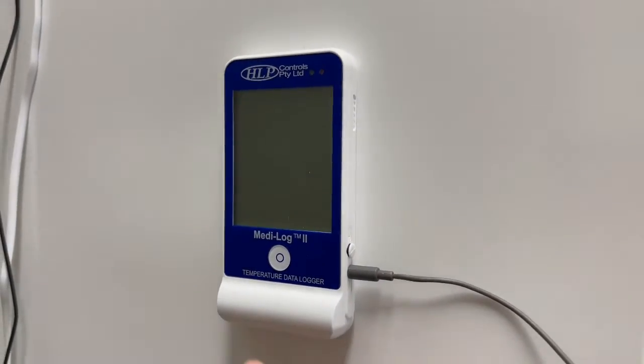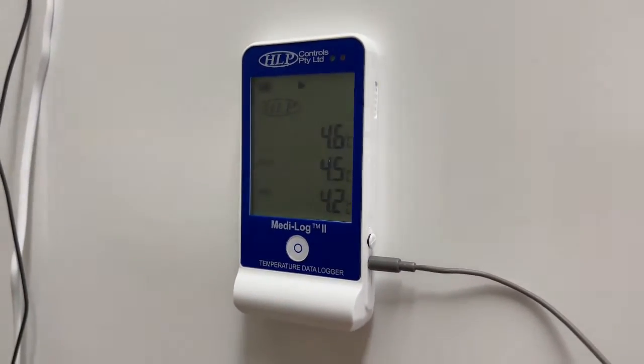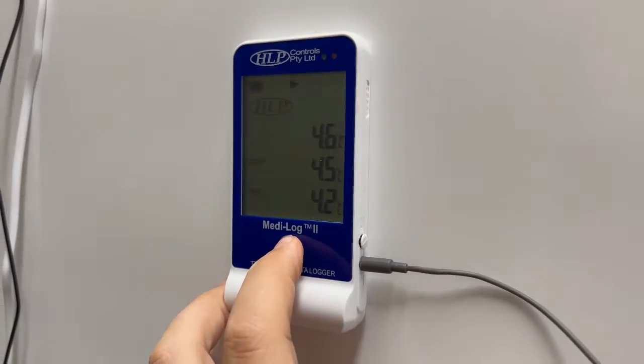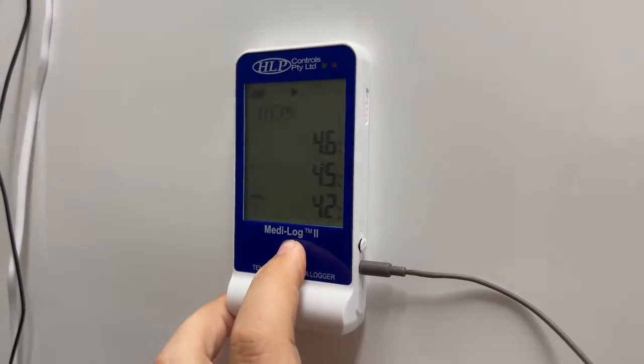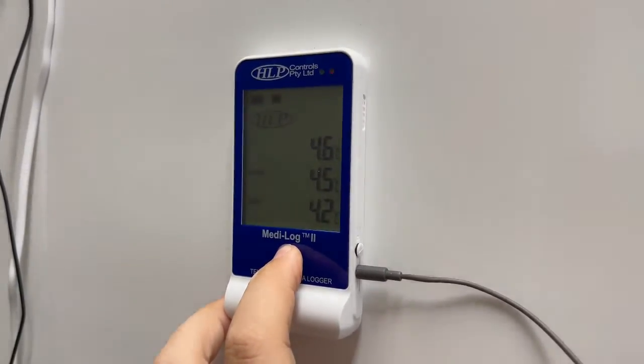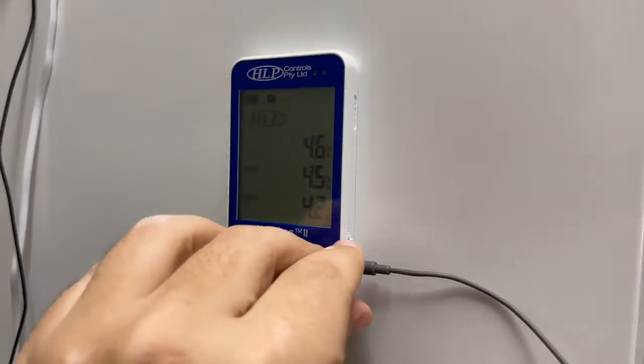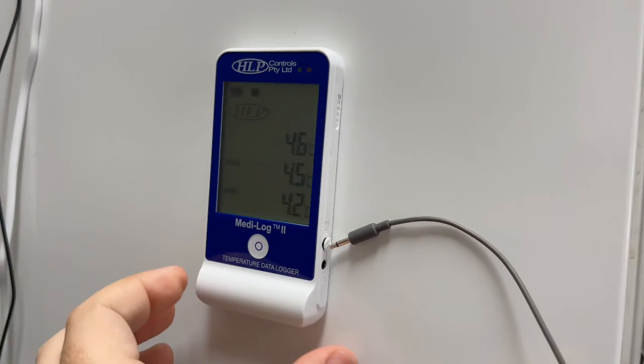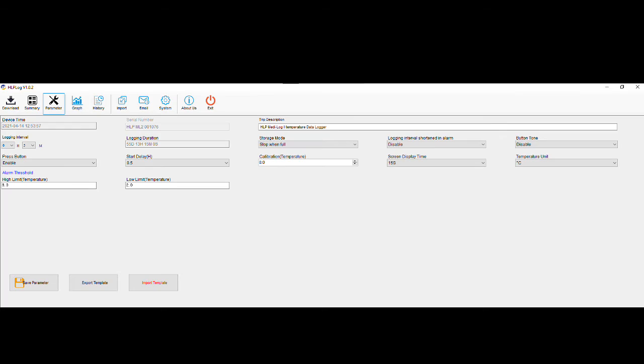Stopping the unit. When you're ready to download the data from the unit, single press the center button to display the LCD screen and press and hold the center button for 5 seconds to stop the unit. The square stop icon will now display at the top of the LCD screen. You are now able to disconnect the probe and plug the unit into your computer. You will not be able to restart the unit until it has been plugged into the computer and the Save Parameters button has been clicked on the Parameters page in the HLP Log app.